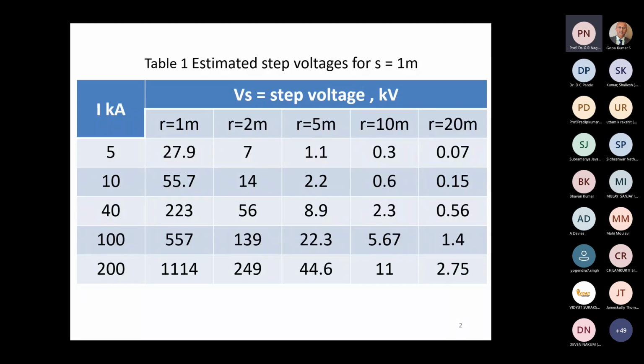If you think of the worst case of 200 kiloamperes, you will see that the step potential is 1000 kV plus at 1 meter, comes down to about 45 kV at 5 meters, and then comes to a very low value of about 2.75 kV at 20 meters. So one simple conclusion we can draw from this table is that if you stay at least 20 meters away, things are very safe, or at least 10 meters away is reasonably safe. That's the best thing that we can say. So the so-called tall pole lightning protection scheme has to be barricaded for this distance.